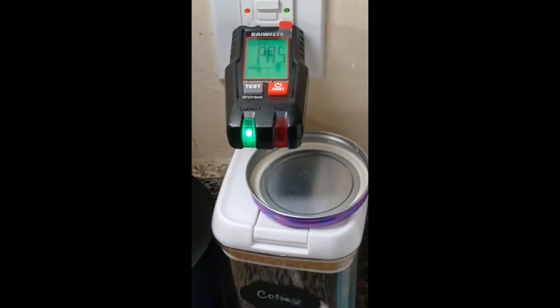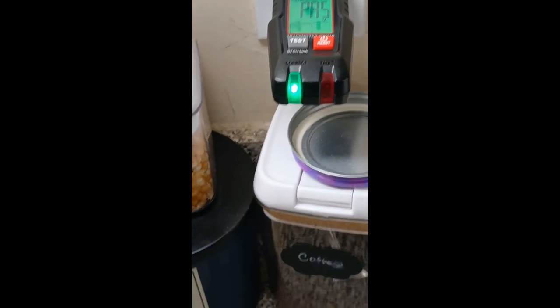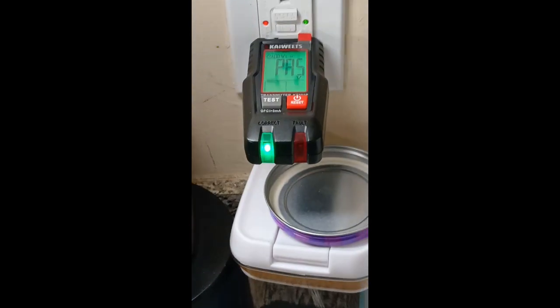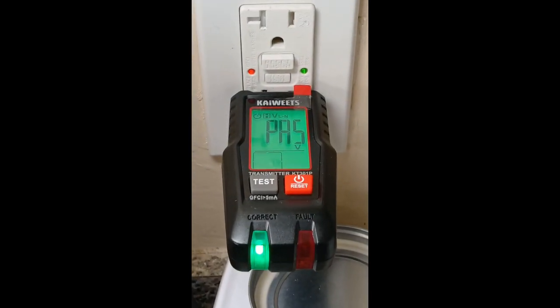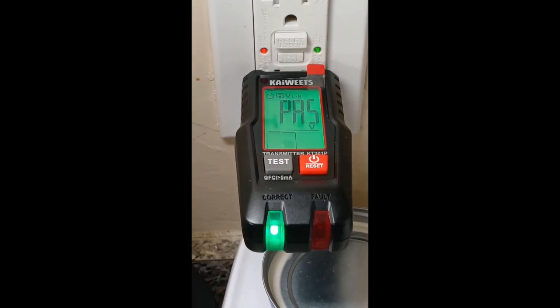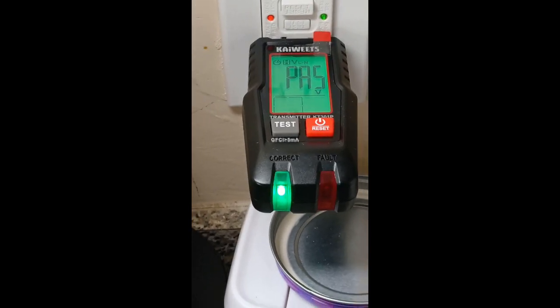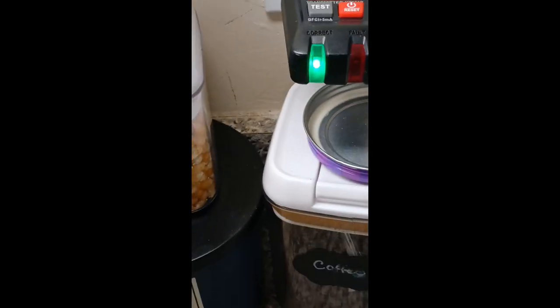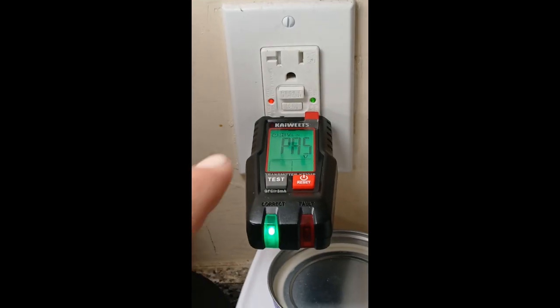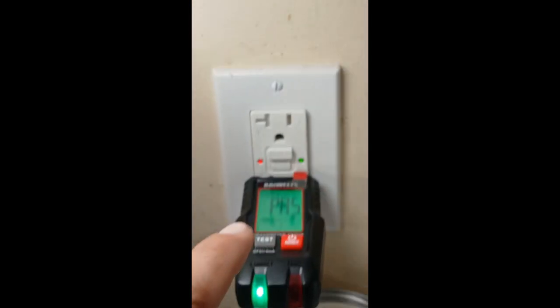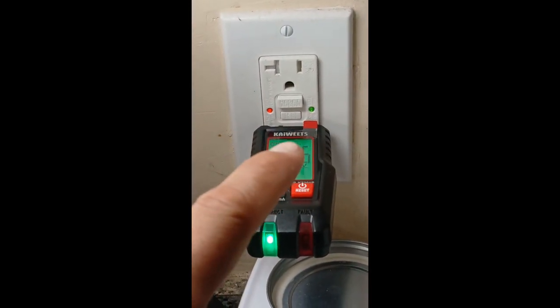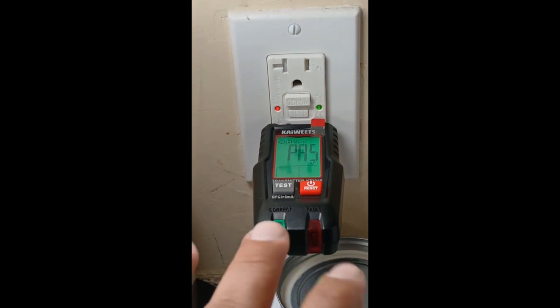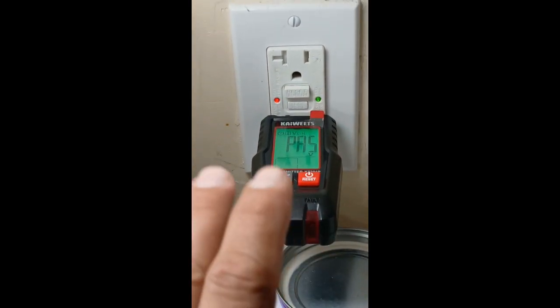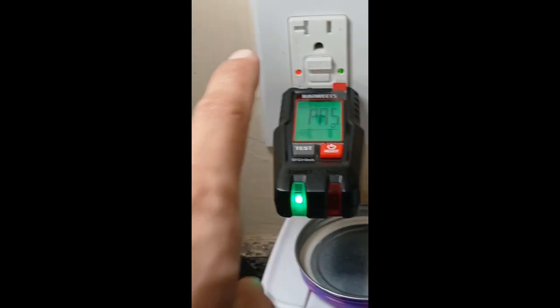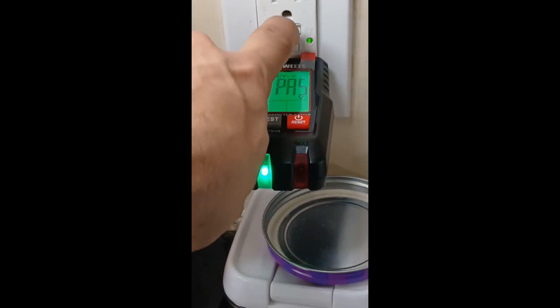Now you can see that the lights are flashing. They were flashing red and green. That's going through the test, and it says on the screen, pass. As you notice, there's no voltage now. There's no voltage passing to the transmitter. All right. So we're going to reset the GFCI, and as you can see, it has its own indication showing power to it. The green means operating normally, red means fault, and if it's green and red, that means it's a tripped GFCI. So all we got to do is hit the reset button. It's kind of tricky though, a little bit. There we go.